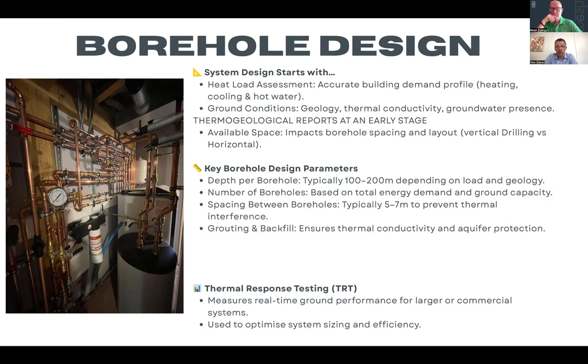That was a large commercial site north of London. So they've already done a TRT test, so we now know what the geology is going to be like. Based on that, they design their system based on the heat load demand, and then use the information from the thermal response test to make the bore field as efficient and suitable for the site, to maintain the output of the boreholes for many years to come.